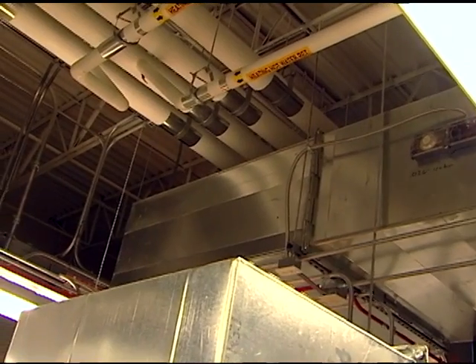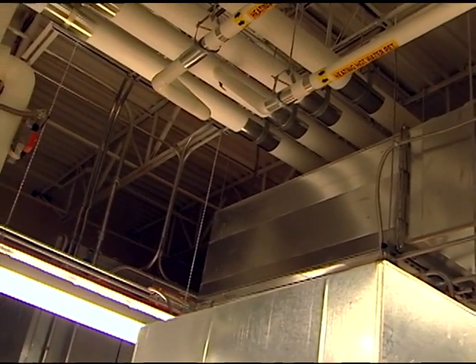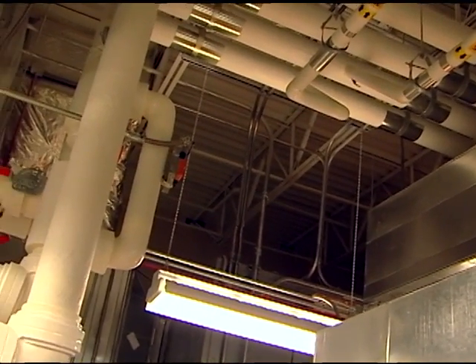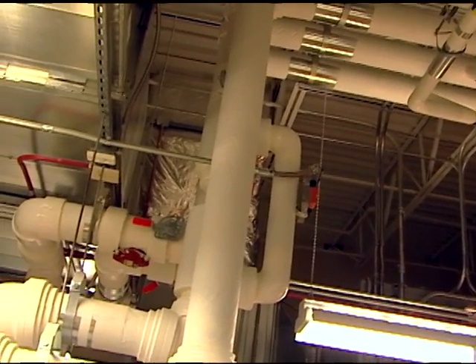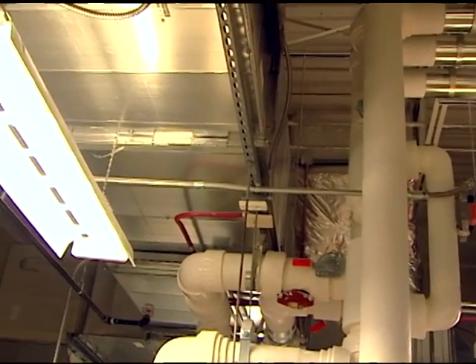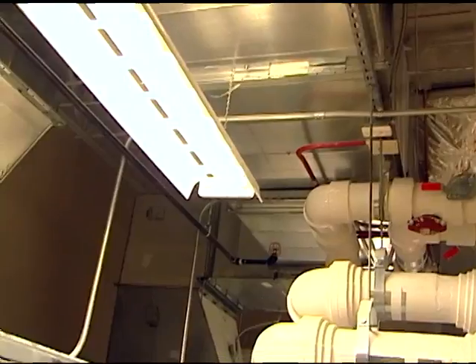The reason for that is sustainability of materials. The ductwork that sends air around this building would be massive—you could drive a car in it if done from one central point. So we've split these rooms into strategic points in each classroom wing of the building, allowing the ductwork and the air and hot and chilled water that come into these rooms to be used very efficiently.